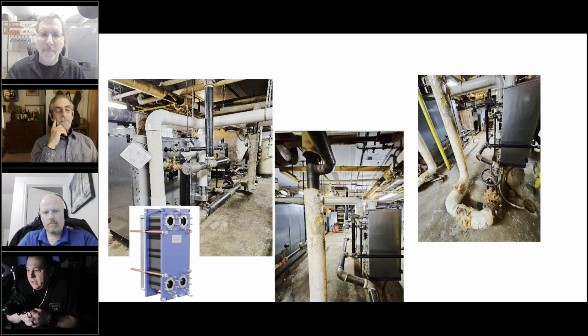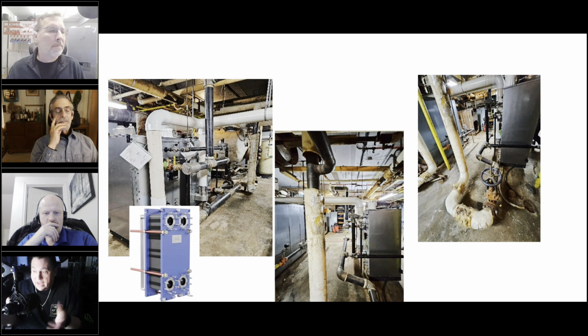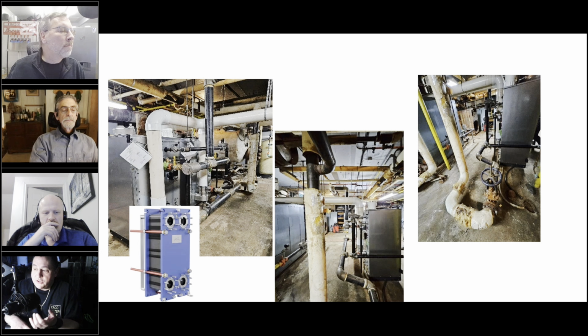So the system wasn't piped that badly. Our internal management team also got the letter I put out, but my recommendation to them and any contractor going into a large building with a bunch of large systems is, number one, the inspector should have said those aren't ASME certified tanks. If a state inspector's out there, he should say you need ASME certified tanks because it's over the allowed amount of BTUs. Number two, if you're not sure, use a plate exchanger on these systems.